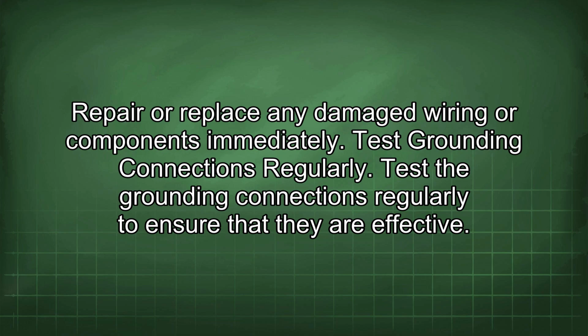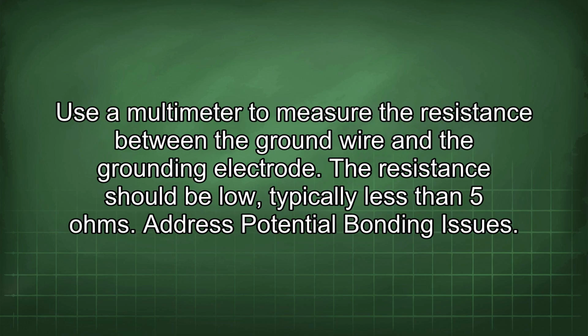Test grounding connections regularly. Test the grounding connections regularly to ensure that they are effective. Use a multimeter to measure the resistance between the ground wire and the grounding electrode.